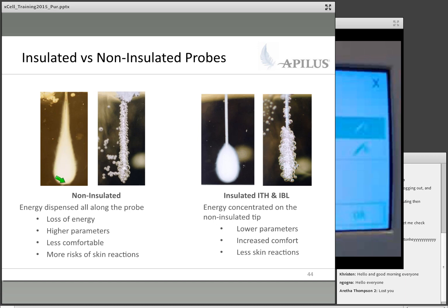As long as the probe is in contact with the skin, there is going to be some energy dispersed in that area. This is high frequency. High frequency has a point effect, and so that means that the higher concentration of energy is always going to be at the tip. But that does not mean that the current doesn't disperse itself up here also. It's just not as intense as it's going to be at the tip. So usually with a probe like that, in order to have a wide enough coagulation pattern, we need higher settings because some of the energy that could be concentrated down here ends up coming out up here. So loss of energy higher in the skin means you need higher parameters. Higher parameters just means it's going to be less comfortable and you're going to see more risk of skin reaction because you have more energy going into the upper layers of the skin. The galvanic does not do the point effect like thermolysis does. So galvanic gets produced evenly along the walls of the probe that is in contact with moisture.